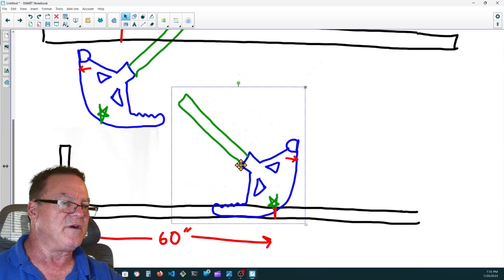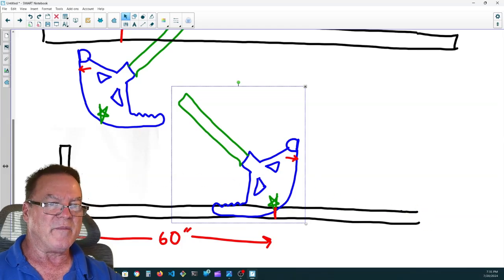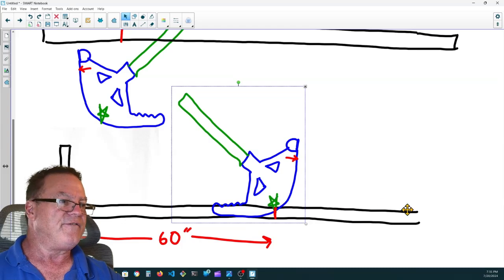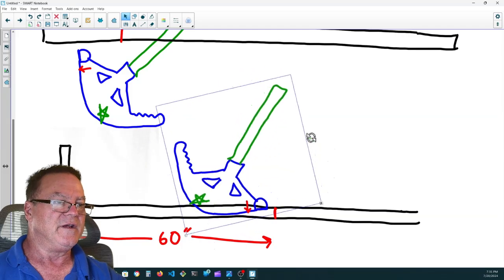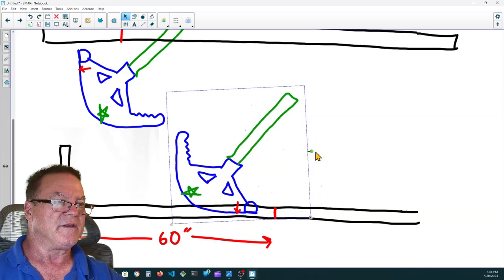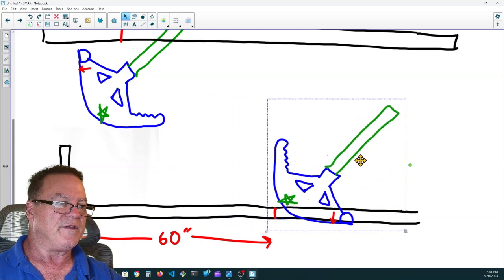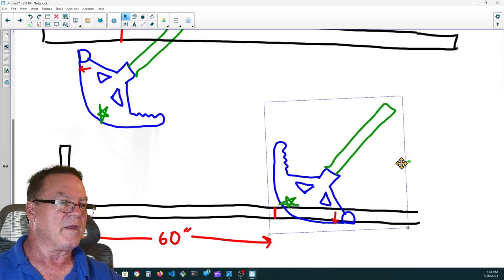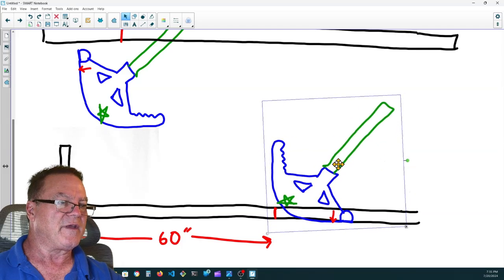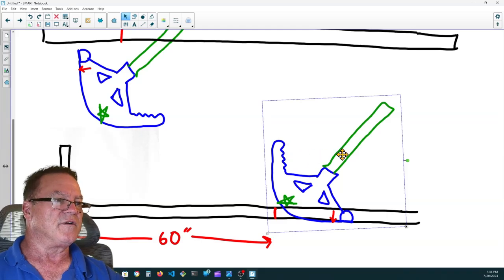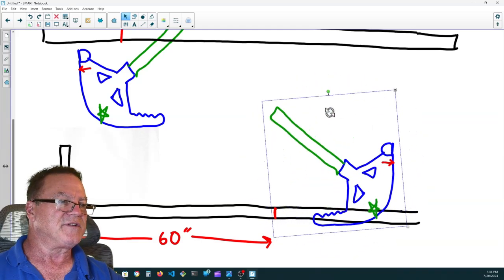And you put this bender on the conduit facing the opposite end from the end you measured from. We measured from the left 60 inches and marked the conduit. We're going to put this bender on the star facing the right end of the conduit. So actually it should be oriented like this. So we'll take this guy and we'll put it on this conduit with this lined up right at that star. And then we'll use our foot pressure and we'll bend up our second 90.